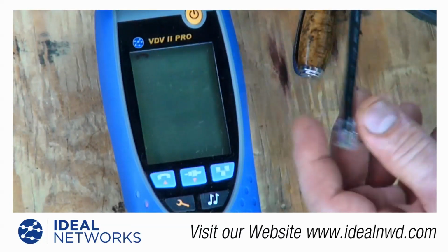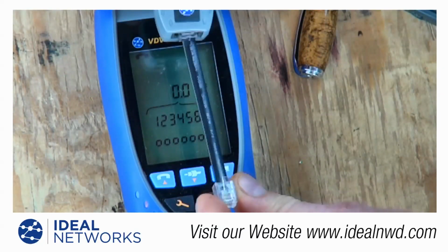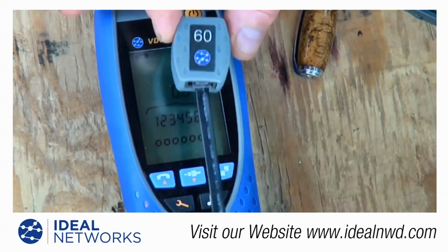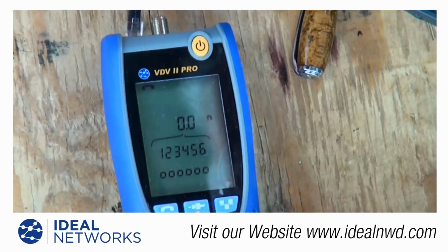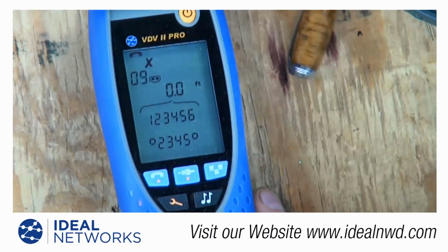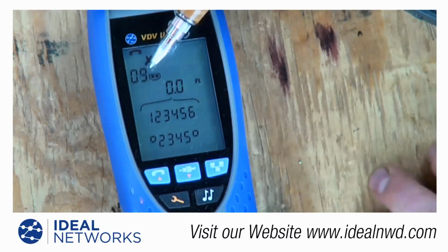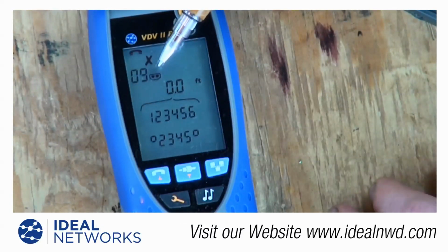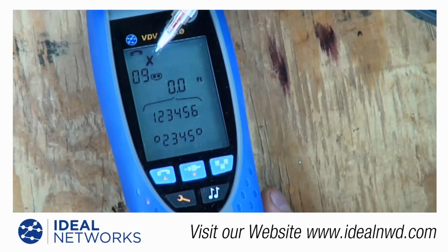I've got a small patch cord with one of the extra remotes plugged into the end of it. If I plug that into the phone port, it indicates it sees the 9th remote on the other end of the cable. The X indicates a bad cable because it sees an open in wires 1 and 6.